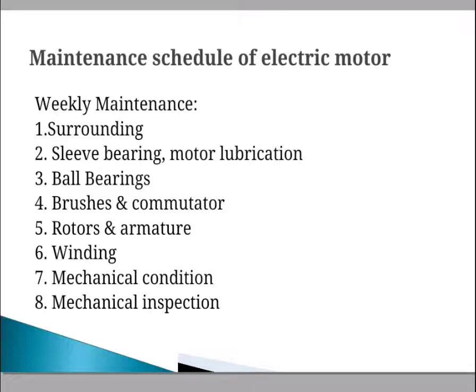Then mechanical condition. Sometimes unusual noise is heard from the motor due to metal-to-metal contact, or scratching of the varnish insulation. Stop the motor, check it, and remove the defects present in the system.